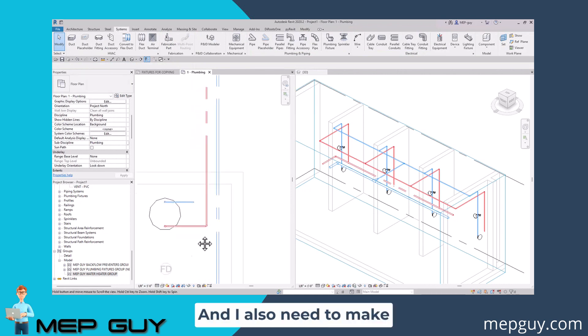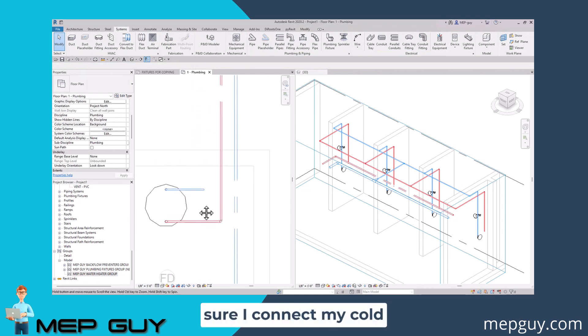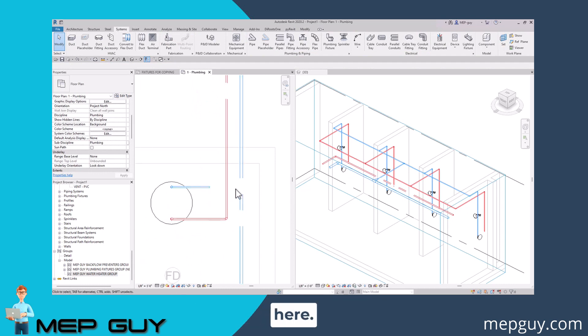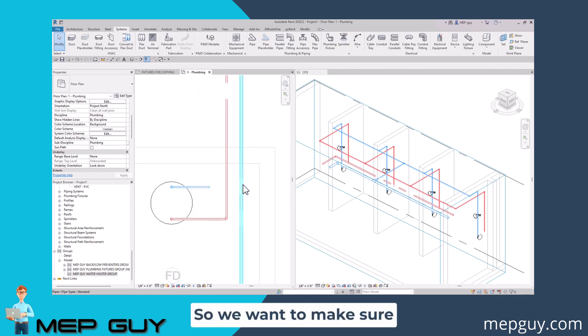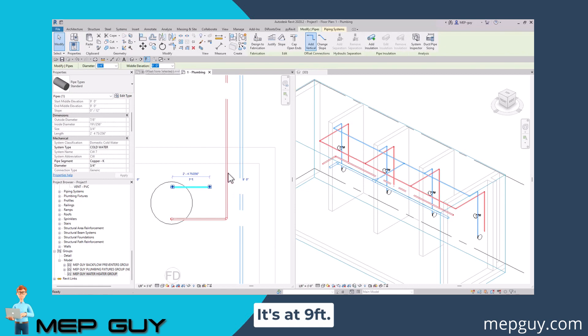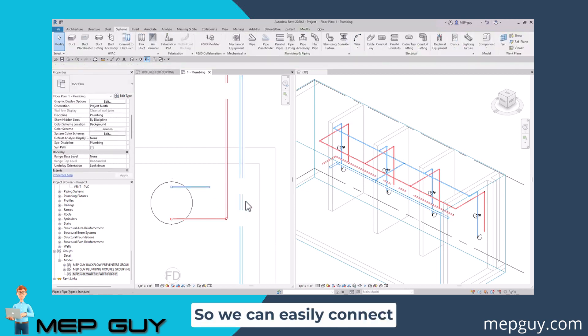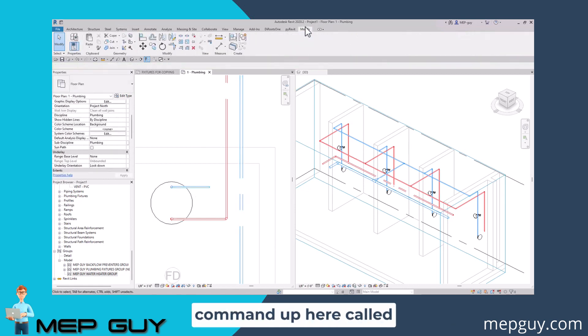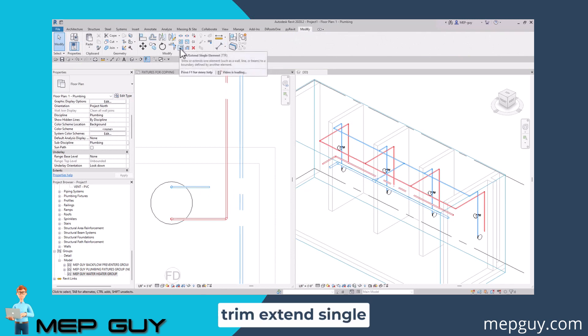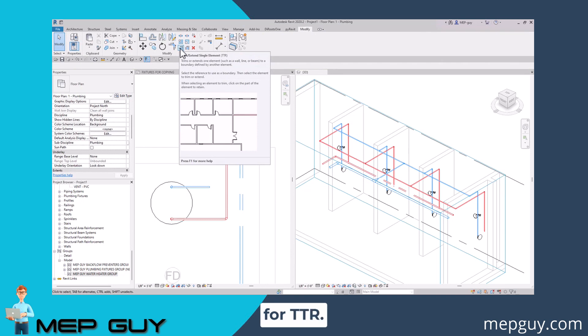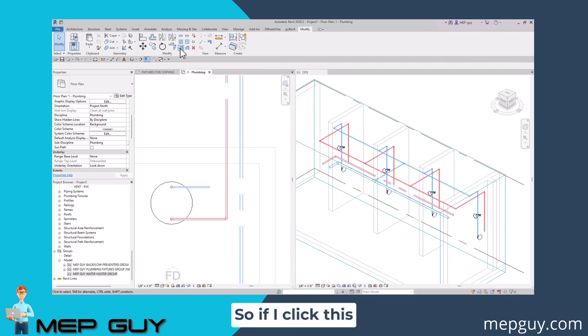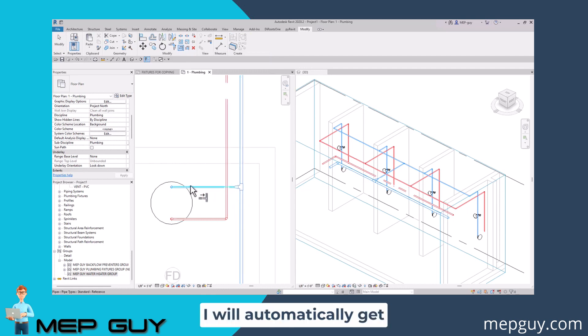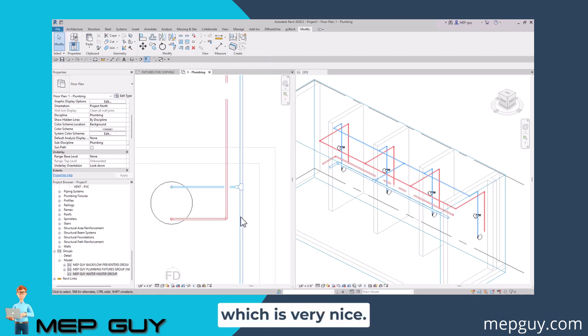I also need to make sure I connect my cold water to this main right here. We want to make sure it's at the same elevation - it's at nine feet. We can easily connect it right into here. We could just drag it or use this cool command up here called trim extend single element. I have a shortcut for that, TTR. If I click this button and click this main and this pipe, I automatically get that connection to be made, which is very nice.